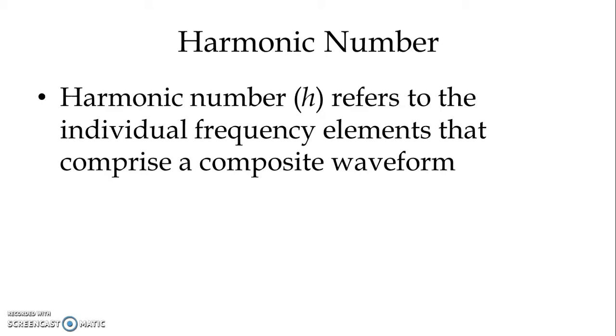We normally refer to harmonic numbers instead of frequencies for two reasons, because everywhere we have different fundamental frequencies. Here we have 50 Hz; in some places we have 60 Hz. In traction we use 25 Hz, in aerospace we use 400 Hz, and in inverters or adjustable speed drives we have from zero up to the fundamental frequency. That is why we use harmonic numbers instead of frequencies.